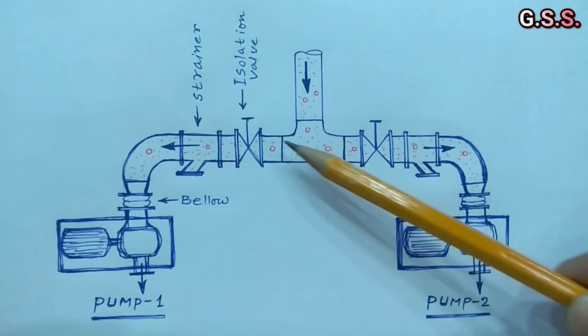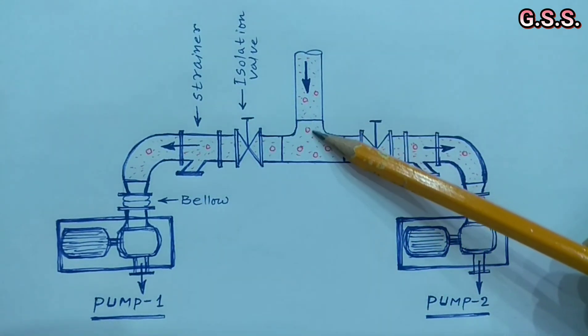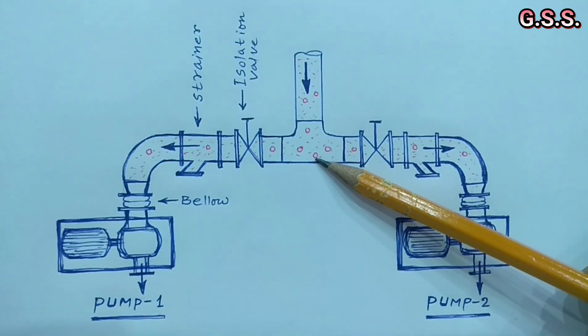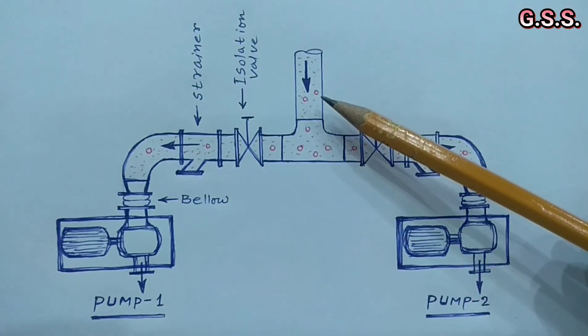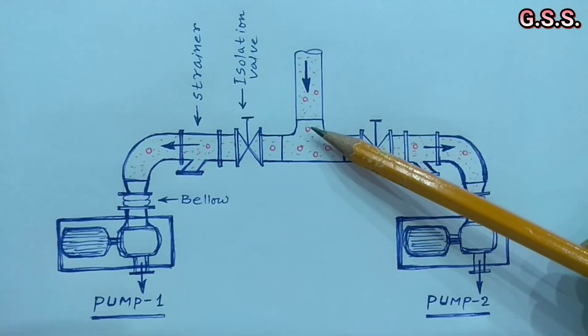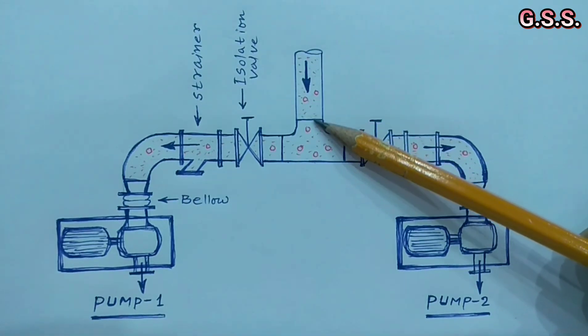But due to this T, flow from branch side hits directly on the T inside and more pressure drop occurs. Also, if any air bubble or vapor is there, liquid with air bubble or vapor will hit the T directly.